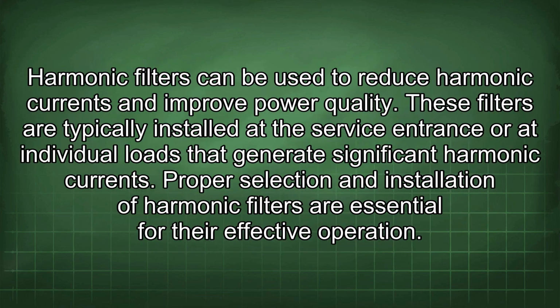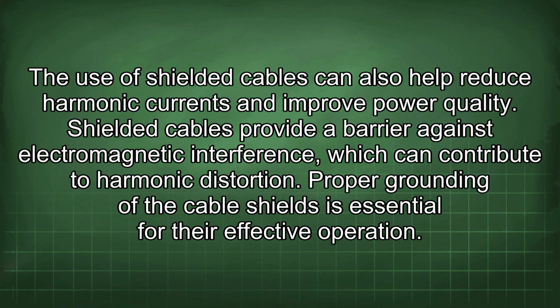harmonic current. Harmonic filters can be used to reduce harmonic currents and improve power quality. These filters are typically installed at the service entrance or at individual loads that generate significant harmonic currents. Proper selection and installation of harmonic filters are essential for their effective operation. The use of shielded cables can also help reduce harmonic currents and improve power quality. Shielded cables provide a barrier against electromagnetic interference, which can contribute to harmonic distortion. Proper grounding of the cable shields is essential for their effective operation.